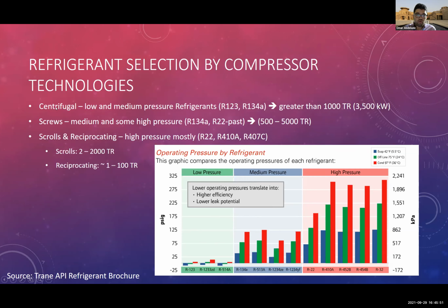And then for screw compressors, this is medium and some high pressure application. Typical refrigerants are R134A and, in the past, R22. This is between 500 and 5,000 tons of refrigeration. For smaller capacities, we call it high pressure, mostly in the past R22, now with R410A and R407C. And you can see here, this is a figure that is captured from the Trane API refrigerant brochure.